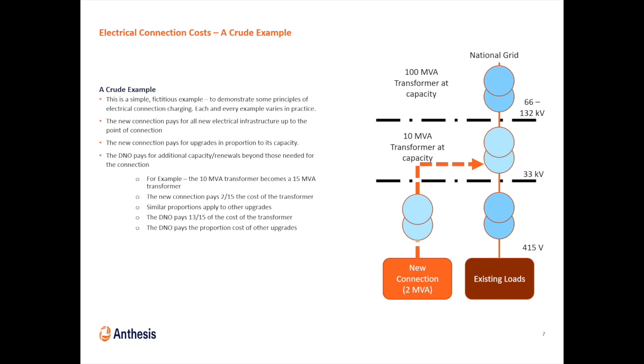For example, if we've got a 10 MVA transformer here and we want another 2 MVA, that might need to go up to, say, a 15 MVA transformer, because you can't necessarily buy a 12 MVA transformer. Maybe you can, but if it goes up to 15, the developer, or the new connector, pays something like 2/15 of the price. The other 13/15 of the price, and proportions of any of the other upgrades this is driving, get paid by the DNO.